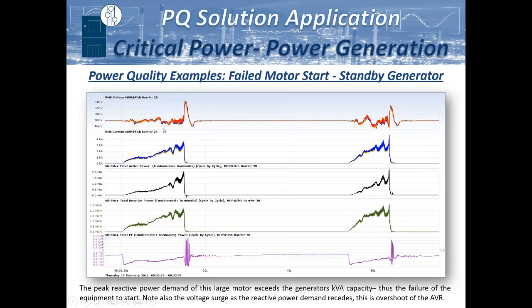So, kind of go through here. This is an example of a failed motor start on a generator network, and you can see that the generators have AVRs, which is automatic voltage regulation, but oftentimes they're very slow in response. So by the time the AVR responds, it's actually after the event is already over. So you can see these large voltage surges because the AVR is responding after the event is actually over with.